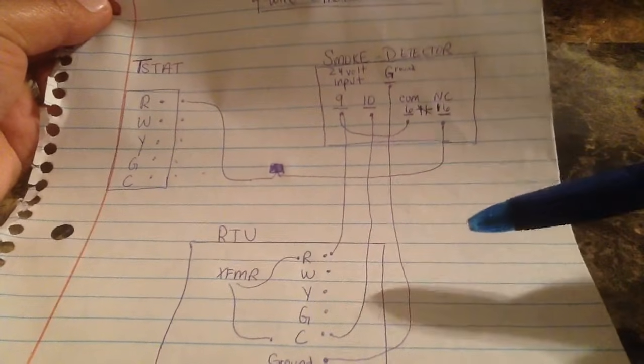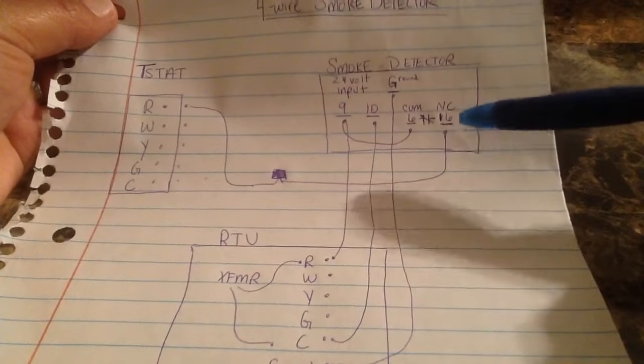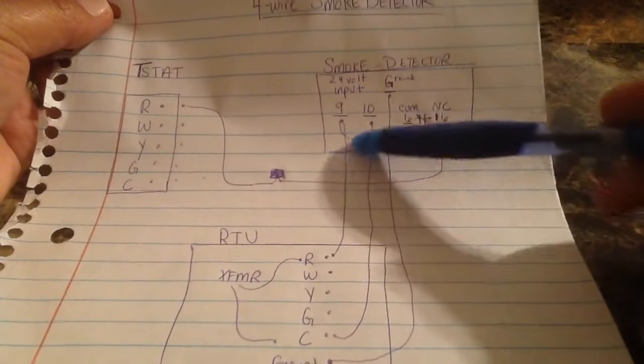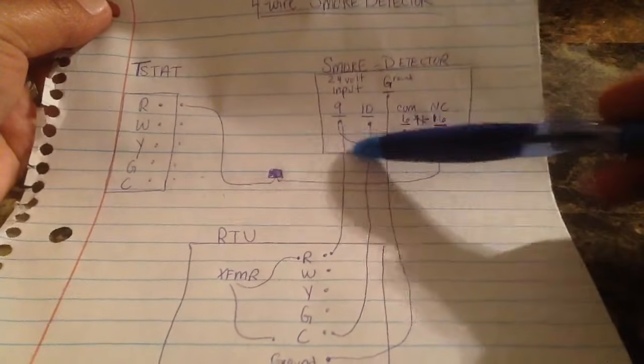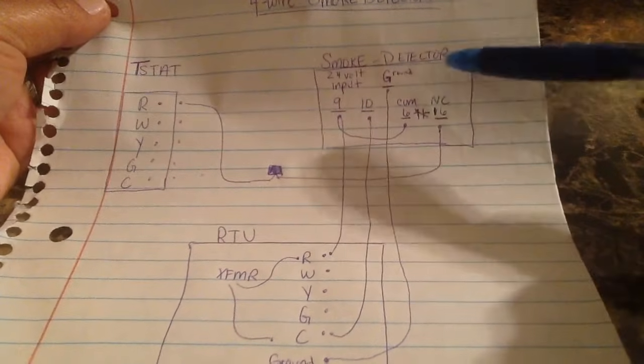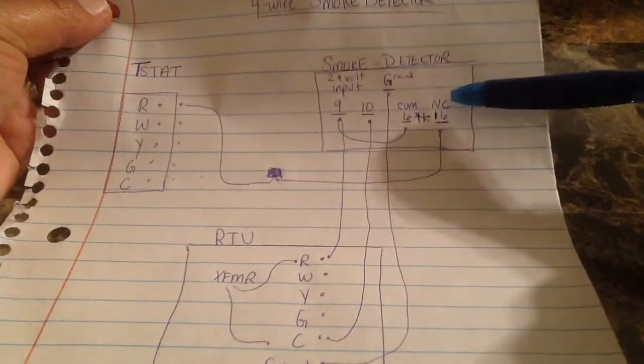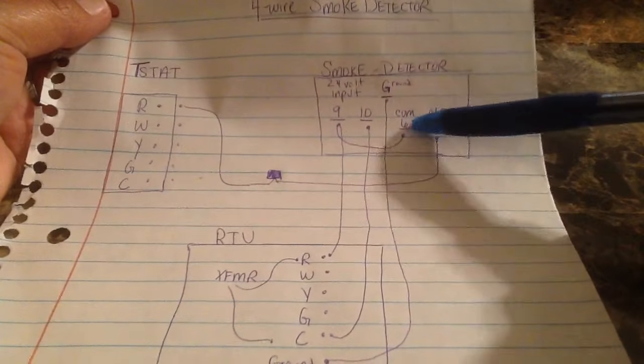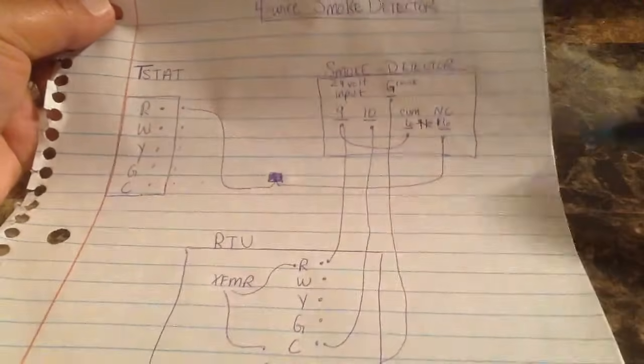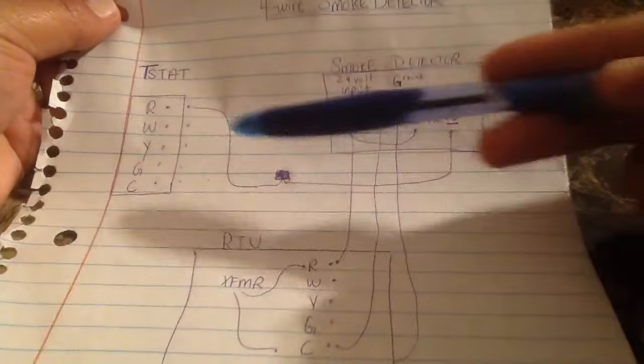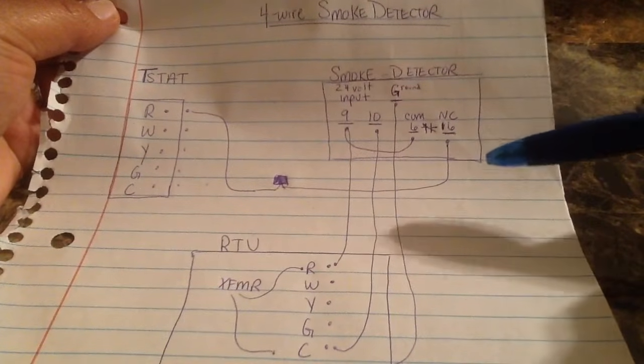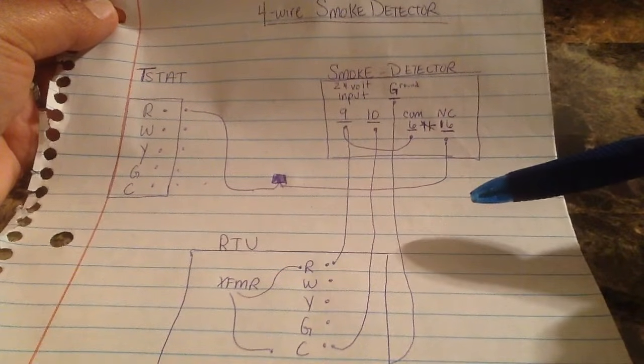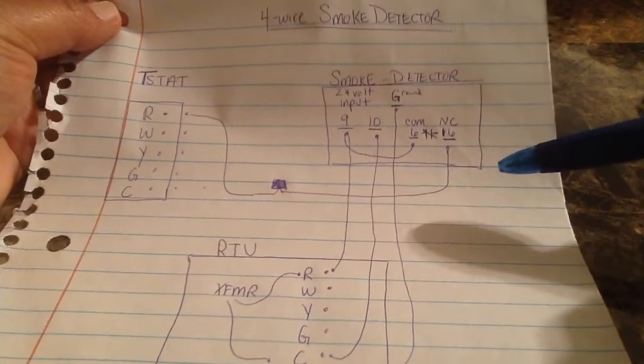So in a situation where there is smoke and the unit needs to shut down, 24 volts comes from the transformer powering up nine and ten, 24 volts comes to six, and this opens up because the smoke detector is now in an alarm state. And this interrupts 24 volt power passing to the thermostat. So thermostat's calling for cooling or heating or fan operation, it's not going to get any juice going over there. So just an easy simplified version of it.